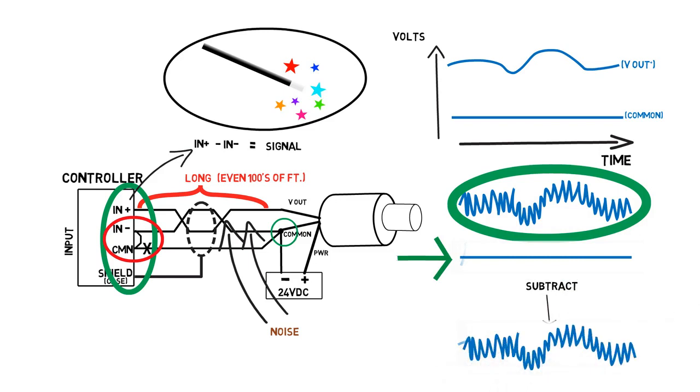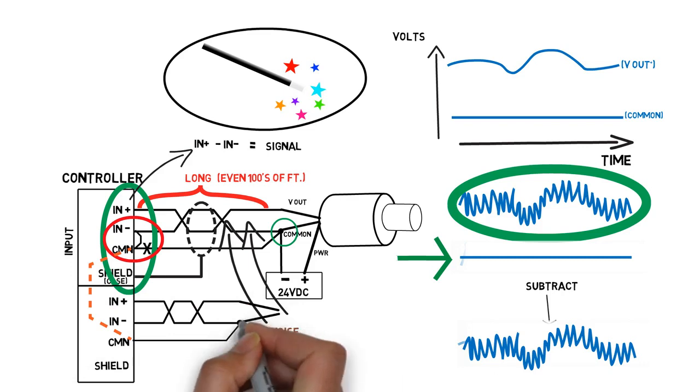If you have multiple inputs, beware of ground loops. For example, if this controller has multiple inputs that share a common internally, and we connect another device in the same way, we will have a ground loop that can generate noise.